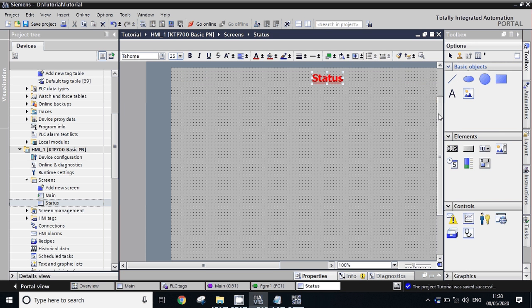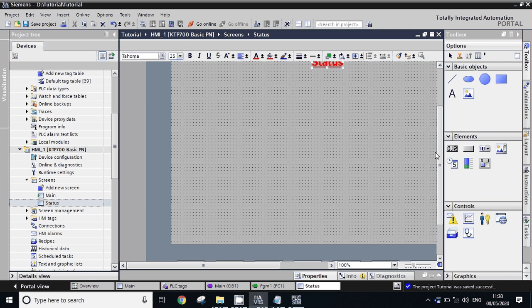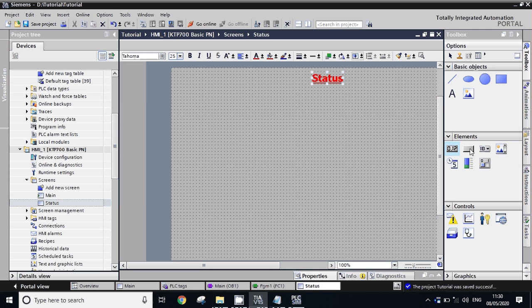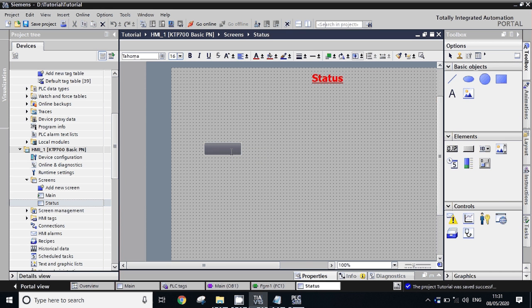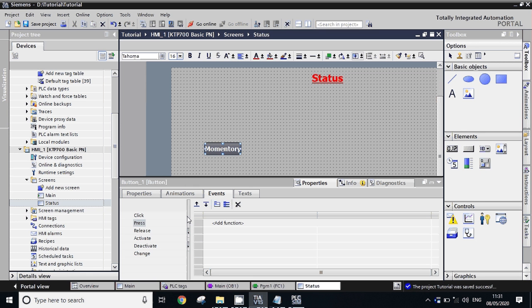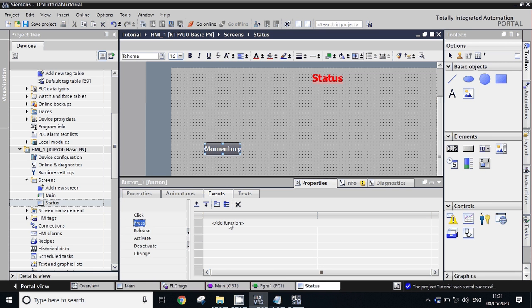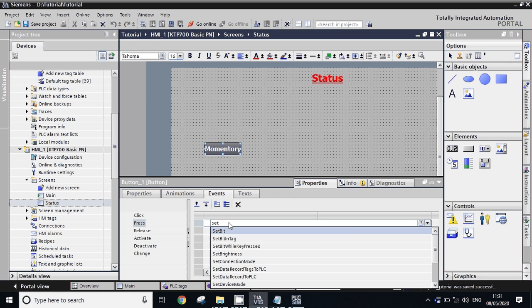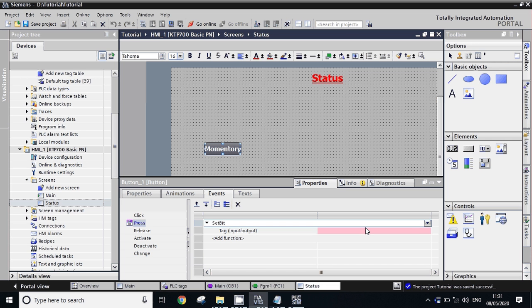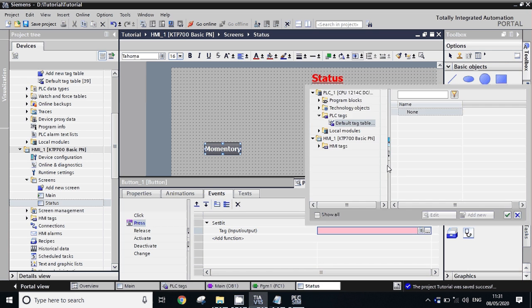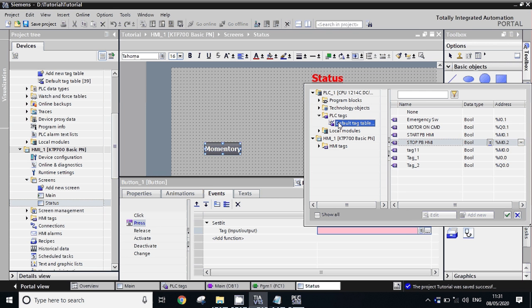Now we will take a momentary button and place it in the middle of the screen. Go to Properties, click on Event. On press, we will write the event as 'Set Bit'. Give the tag name here — click here so we will have our tag list. Go to PLC Tags and take M0.1.